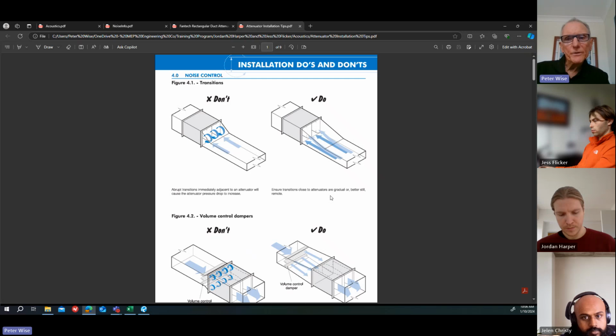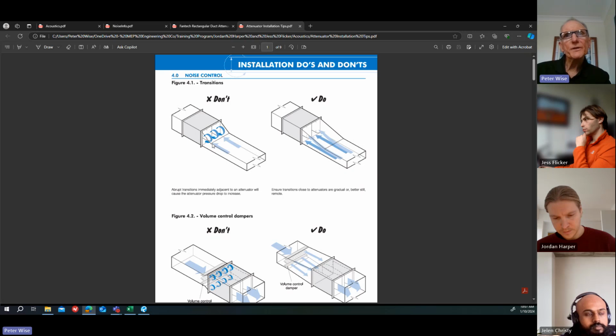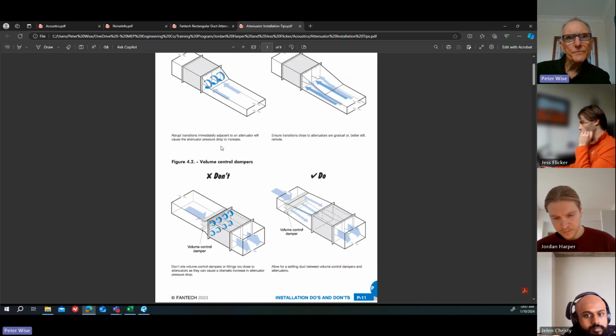These are installation do's and don'ts, they call them. We've talked about these from the point of view of fans before, but these are for attenuators specifically. So left side, don't do this. Right side, this is a better way to do it. The left side in this case, they've got a sharp transition at the inlet to the attenuator. They're saying don't do that because that's creating turbulence. Provide a long transition so that the air has got room to expand into that volume before it hits the attenuator. What tends to happen if you have a short transition like this and the air is traveling along quickly, it just doesn't have time to expand to cover the full face of the attenuator before it goes in. So that's pretty straightforward.